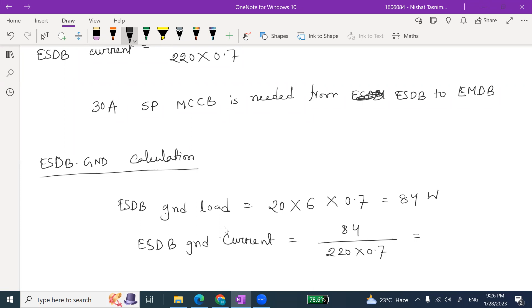0.54 ampere. So you can see basically from the table that the lowest is 1.5 RM, right? Lowest is 1.5 RM, table 5 ampere rating. So we can say we will use 5 ampere SP MCCB as circuit breaker and 1.5 RM cable. Okay. Now we need to include these things in the connection diagram. Now let's get back to the connection diagram.